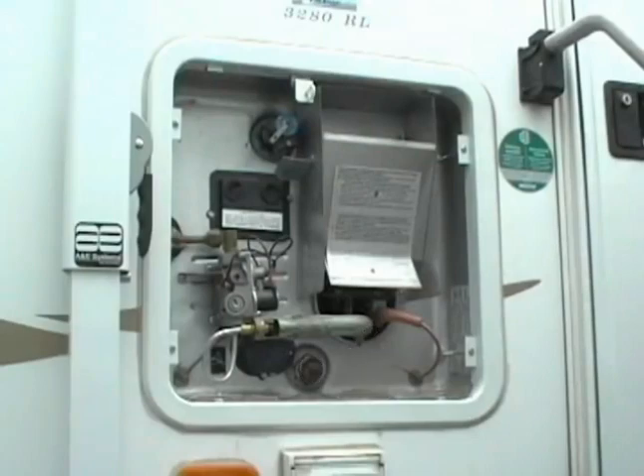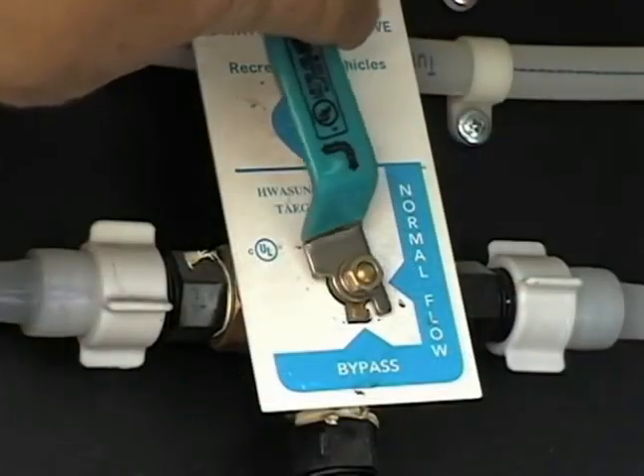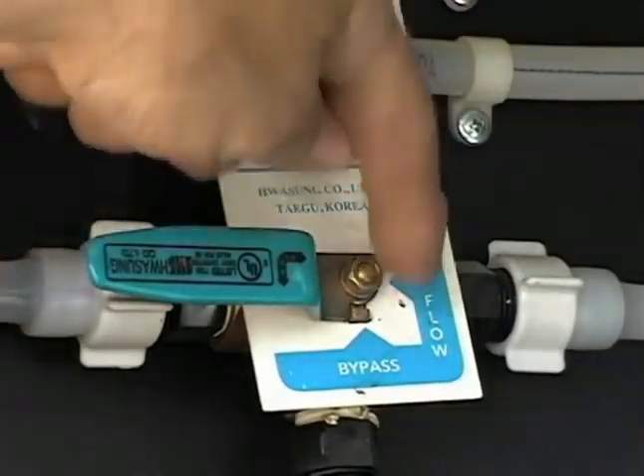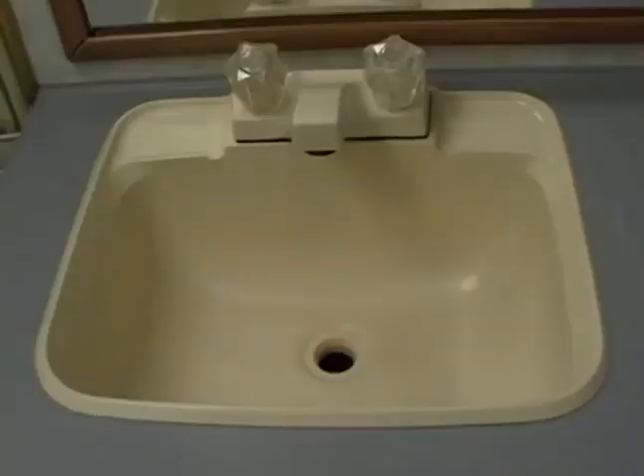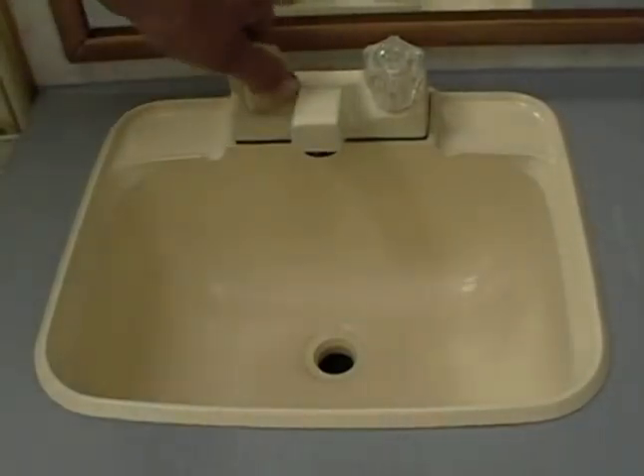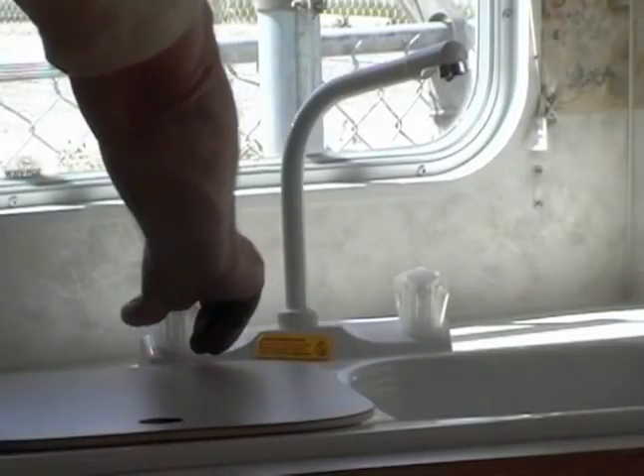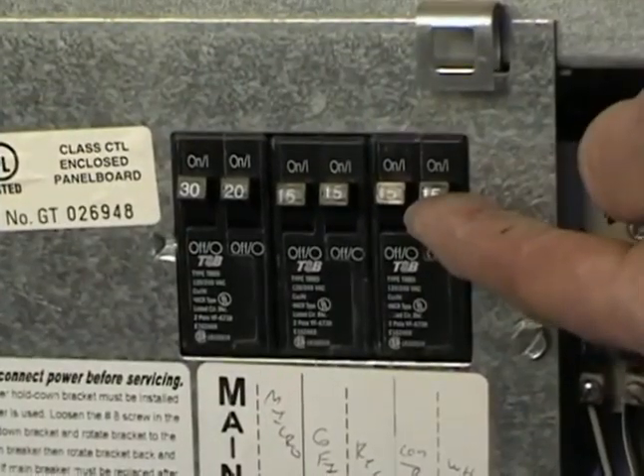Now we can reverse the bypass valve or valves and allow the hot water tank to fill. You'll have to open a hot water tap in order to get the air out of the tank. When the hot water tank is full and no more air comes from the tap, shut off all taps and light the heater and turn on the circuit breaker for the electric heater.